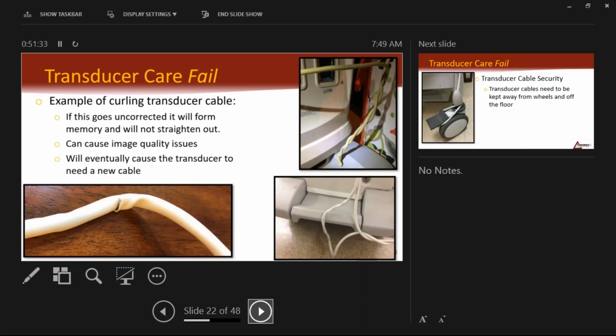So here's a couple examples of twisted cables on transducers. So we've got this one, not so bad. There's a little bit of twisting going on there. This one is horrific. I took this picture. I wouldn't even try to straighten it. I couldn't. I felt like if I straightened it, the probe was going to stop working. And from the time I took that picture, the probe lasted about another 18 months and then died. And I don't know whether it was the cable or not.